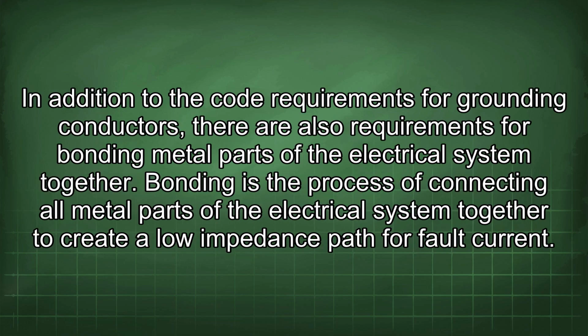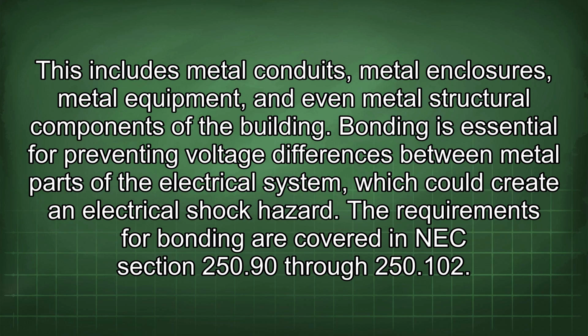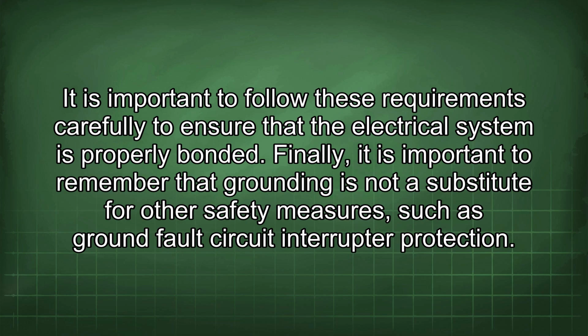In addition to the code requirements for grounding conductors, there are also requirements for bonding metal parts of the electrical system together. Bonding is the process of connecting all metal parts of the electrical system together to create a low impedance path for fault current. This includes metal conduits, metal enclosures, metal equipment, and even metal structural components of the building. Bonding is essential for preventing voltage differences between metal parts of the electrical system, which could create an electrical shock hazard. The requirements for bonding are covered in NEC section 250.90 through 250.102. It is important to follow these requirements carefully to ensure that the electrical system is properly bonded.